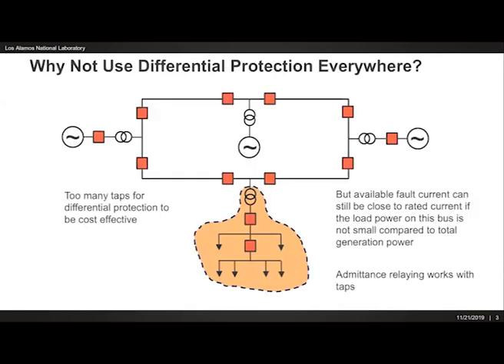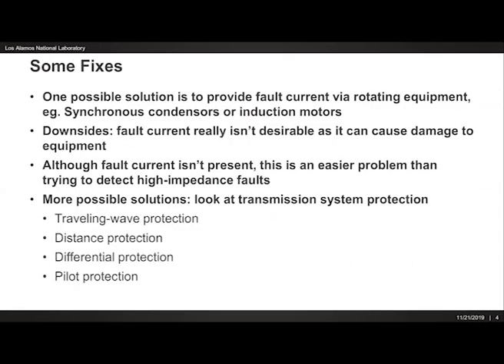So the first question that came to me is, why don't they use differential protection? The answer is, for microgrids which have a large number of load taps, if they're supplying an industrial facility or residential area, we wind up with radial lines coming off of them, where there's a sufficient number of nodes that we can't cost effectively provide differential protection on every line. So this steered me in the direction of admittance protection. However, it's certainly not the only possibility.